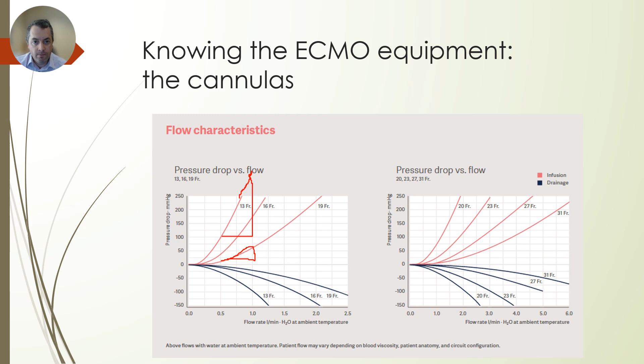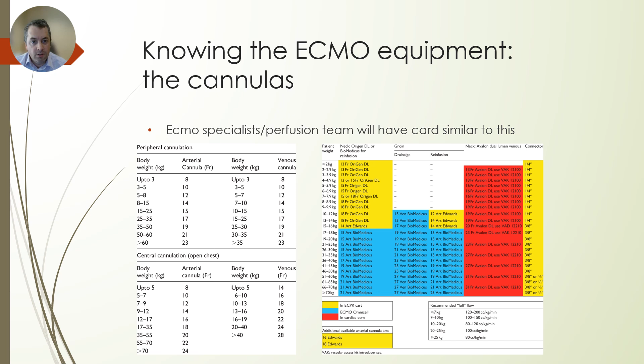Sometimes in shock, those vessels can appear smaller, but they will be able to accommodate a larger cannula. And so it's a good idea before cannulating to talk to your ECMO specialist or perfusionist and see what kind of flows you're going to be needed for the condition that you're trying to treat, and what size cannula you should try to target to meet those demands. Those folks will have a card that looks something like this based on the cannulas that they have in stock at your facility, and it'll tell roughly based on weight what size cannula is appropriate. Keeping in mind that some conditions, for example, certain cases of septic shock may want higher flow and may need larger cannulas.